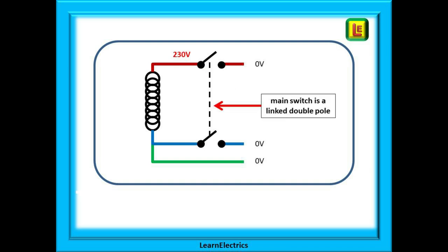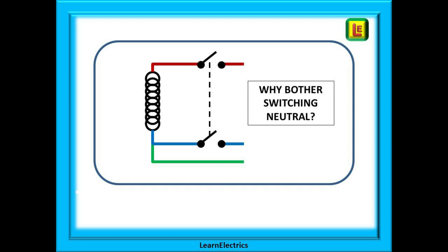This means that if you turn the main switch off in the consumer unit, one half of the main switch is still energized. Most main switches are double pole. They are linked together so that they switch off both live and neutral at the same time, and this is a requirement in all domestic properties. But why bother switching neutral if it is zero volts?